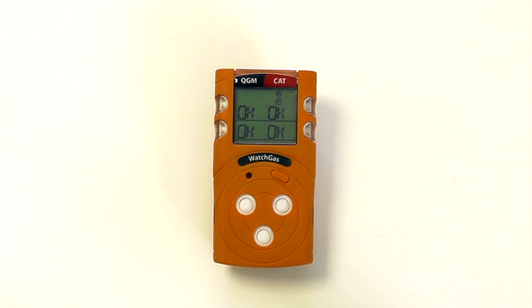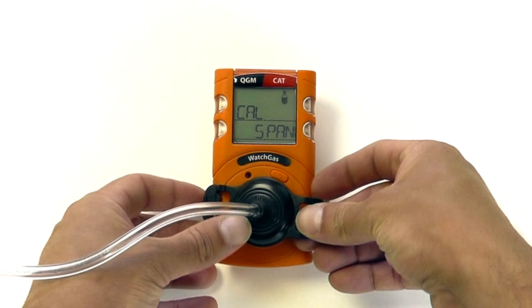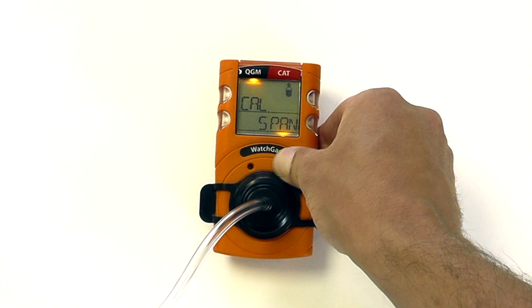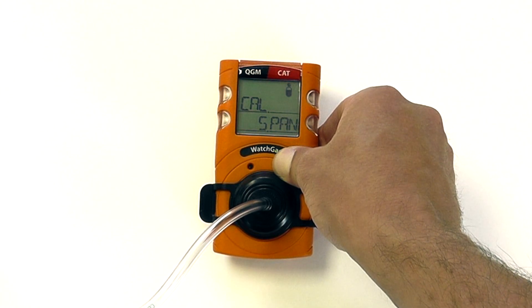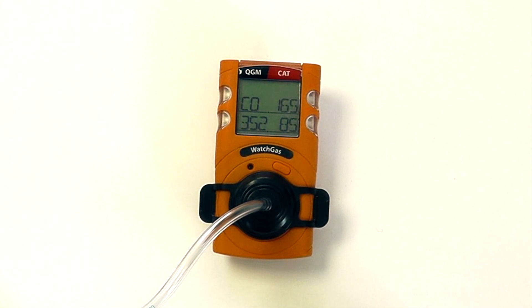Once the zero is complete, you will be given the option to do a full span calibration. Skipping over to cal span, we can apply the calibration cap. Should we wish to do a user calibration, press and hold the button and open up the calibration gas. It will then take 90 seconds to perform a full span calibration on the sensors. As we can see, the calibration has completed successfully and all sensors are okay. We can now remove the calibration cap and we are back in normal operation.